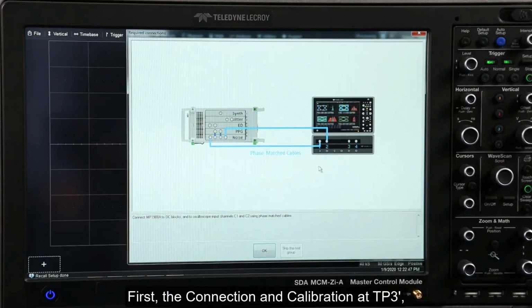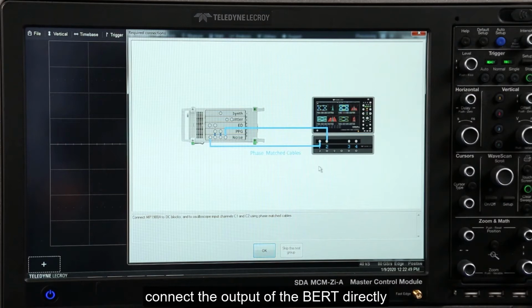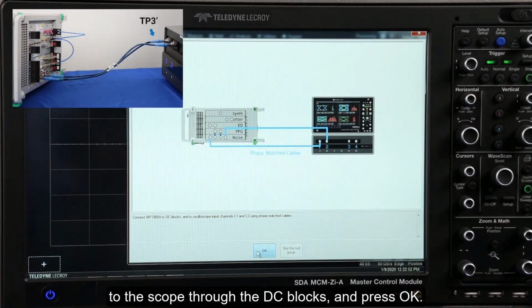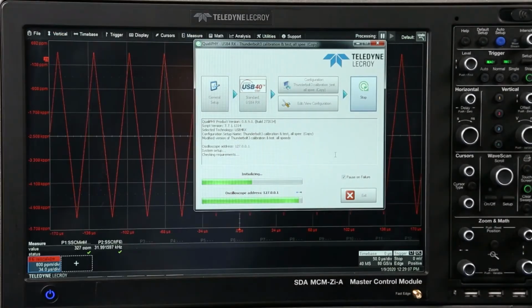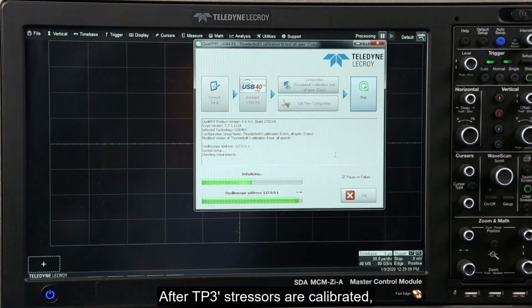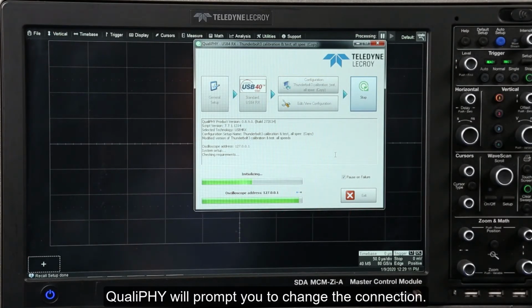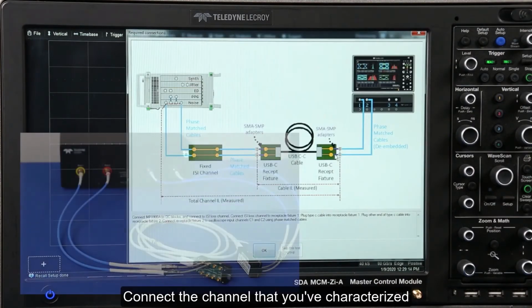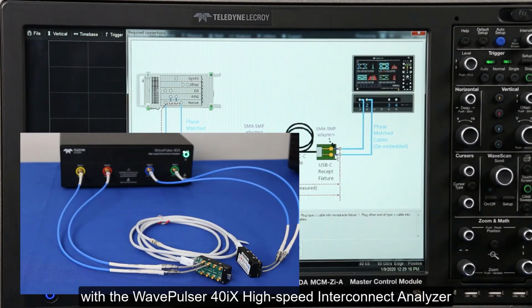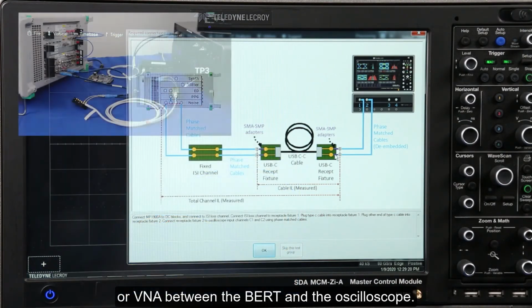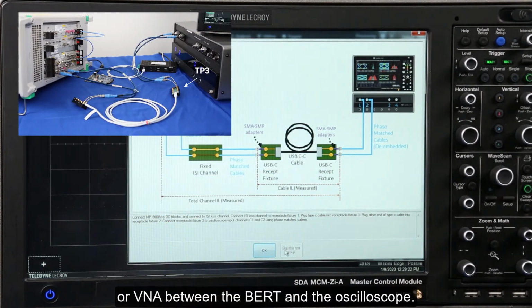First, the connection and calibration at TP3 prime. Connect the output of the BERT directly to the scope through the DC blocks and press OK. After TP3 prime stressors are calibrated, QualiPHY will prompt you to change the connection. Connect the channel that you've characterized with the WavePulser 40iX High-Speed Interconnect Analyzer, or VNA, between the BERT and the oscilloscope. Then press OK.